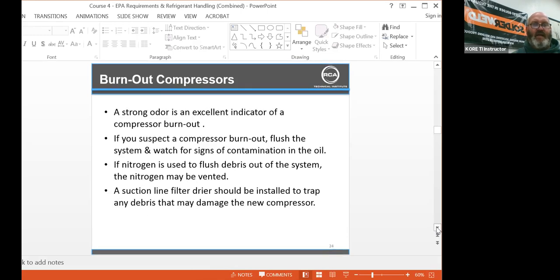A strong odor is an excellent indicator of a compressor burnout. If you suspect a compressor burnout, flush the system and watch for signs of contamination in the oil. If nitrogen is used to flush debris out of the system, the nitrogen may be vented. A suction line filter dryer should be installed to trap any debris that may damage the new compressor. This is simple stuff. You smell the refrigerant. When it burns the inside of your nose and your eyes water, you know you got a bad thing, bad gas. Or you can use a refrigerant test kit and do an oil sample.